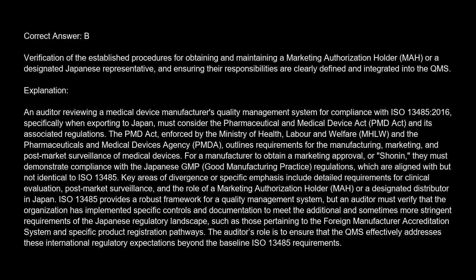For a manufacturer to obtain a marketing approval, or Shonin, they must demonstrate compliance with the Japanese GMP, Good Manufacturing Practice, regulations, which are aligned with but not identical to ISO 13485. Key areas of divergence or specific emphasis include detailed requirements for clinical evaluation, post-market surveillance, and the role of a marketing authorization holder, MAH, or a designated distributor in Japan.